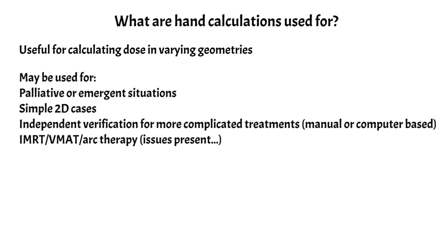But you really start to run into issues with arc therapy, because in arc therapy your SSD is constantly changing as the gantry is rotating, the depth is also changing across the beam, and the field size might be changing as well. So you might need to use some sort of average value for the field size. It's pretty hard to apply the hand calc formalism in some cases, and in fact it might actually break down completely.